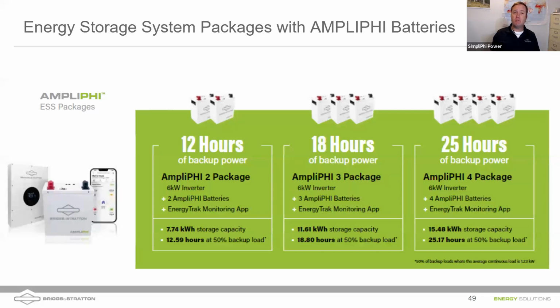Our batteries have a C/2 discharge rate, meaning we can charge or discharge the batteries in 2 hours. So theoretically, with a large enough charger, inverter, and generator, you could charge the batteries in 2 hours, shut the generator off, and get yourself another 18 hours, or 12 hours, or 25 hours. I'd always suggest starting with more hours when sitting down with the homeowner, then you can back the packages down as people understand their budget constraints.